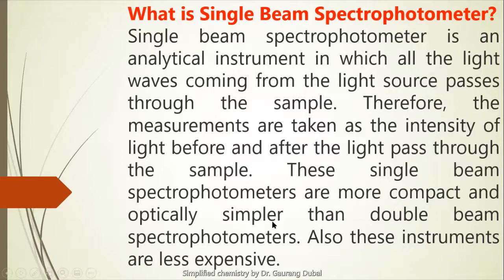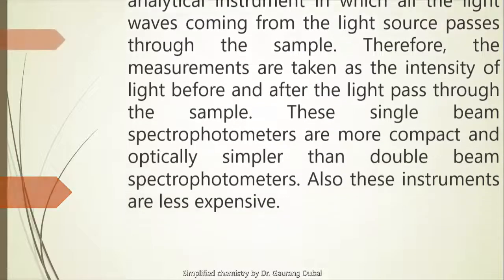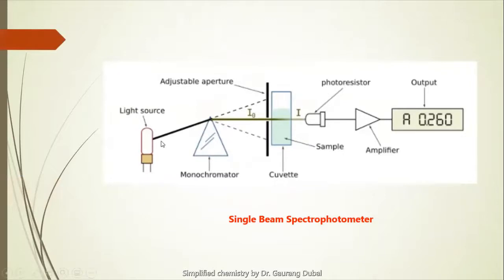These single beam spectrophotometers are more compact and optically simpler than double beam spectrophotometers. This device is comparatively simpler and also less expensive than the double beam spectrophotometer. Here is the schematic diagram — you can see the light source generating light, going to the monochromator, making the light monochromatic, and passing directly to the sample cuvette.